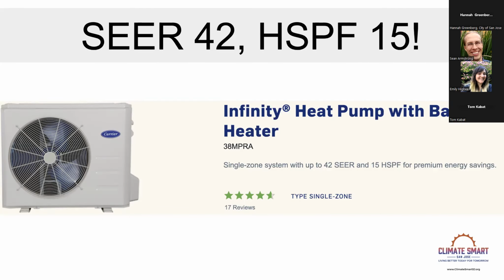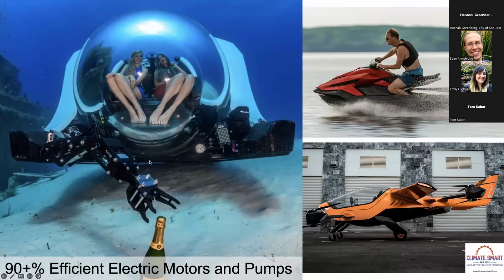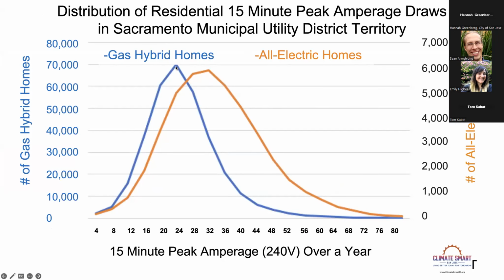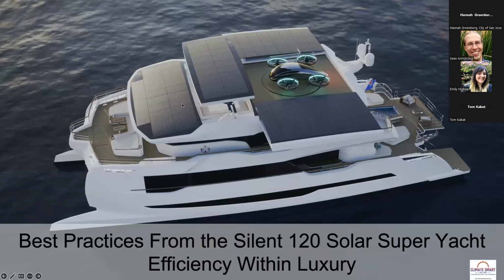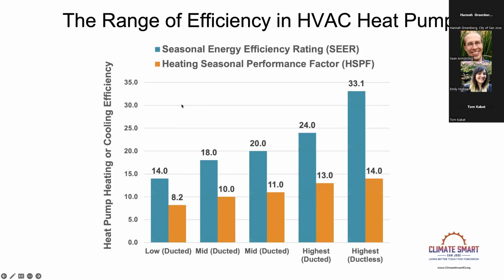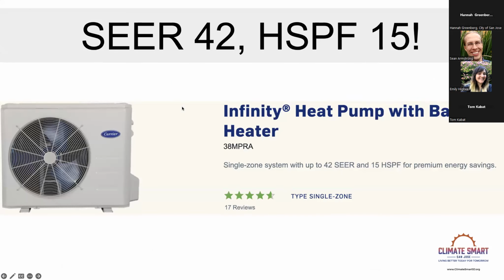So 1/3 as much air conditioning. This is really important to think about for the grid. Going back to these gas hybrid homes, which have their peak because of air conditioning, that's the peak that's going on. This electrical peak is an air conditioning peak. When you put in a super efficient space heating system, like an HSPF 10 or better, you're already lowering the peak in the house, the air conditioning peak. This is what SMUD has seen, that putting in decent heat pumps for space heating has lowered their summer peak. That's awesome, these higher efficiency systems are reducing their actual crisis.